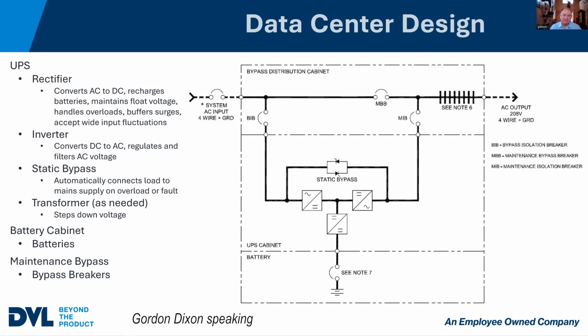We're talking about high voltage equipment. There are codes in place that say you can't open up a 480 volt piece of equipment while it's powered. And if you've got critical components, servers, desktops, or other life safety things downstream of this UPS, you won't be able to do any maintenance on the UPS itself without shutting all of that down, unless you've got a maintenance bypass.